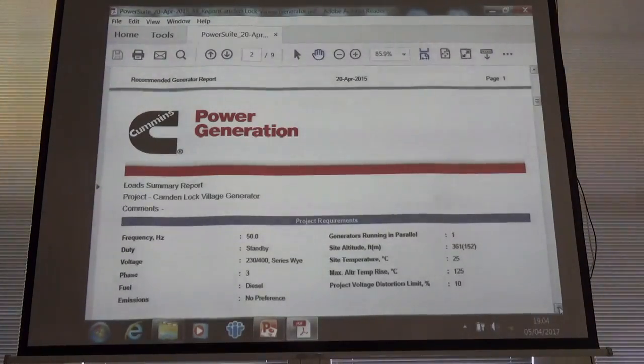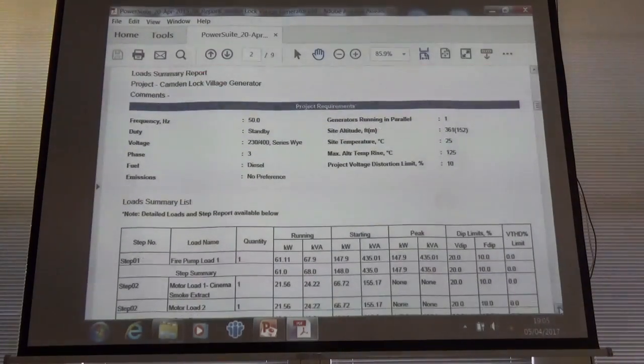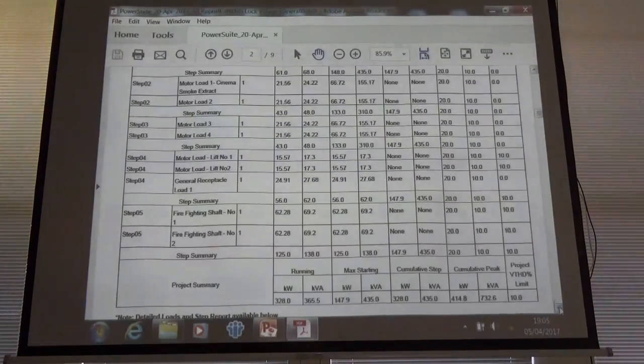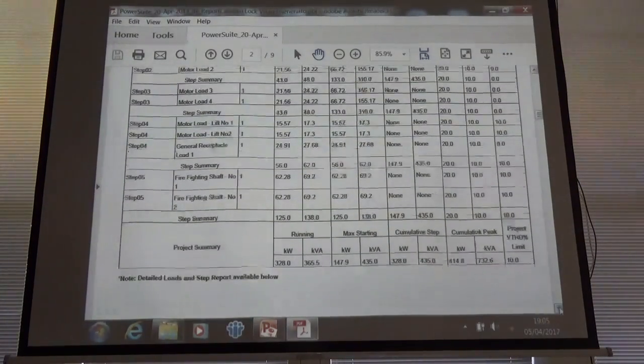So what you're considering is two key elements. The alternator, suitable size of alternator, i.e. the amount of copper it's got in it. You've got obviously excitation systems, you want a PMG and AVR, which gives you the best performance, or the AREP system, which is additional windings in the stator, which is still independent, because the old type generators would take the excitation feeds off the load line. So if you've got a load that's dropped on, it's like a cascade effect. So you need independent generation. So in other words, your exciter section is independent of what's happening on the load supply side. So that's key. Please just ask the questions.